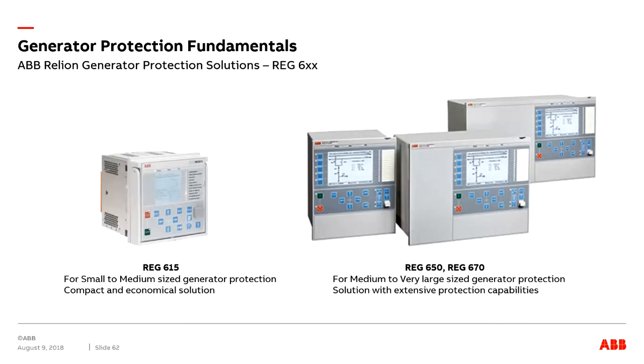Okay, ABB provides several solutions for generator protection from the Relion family, which is called REG. As you can see, G stands for generator protection, and there are different devices available that can be chosen depending on the size of the machine. REG615 is for small to medium-sized generators, and REG650 and 670 are for large to very large machines.